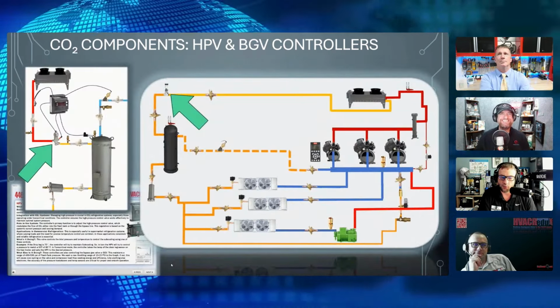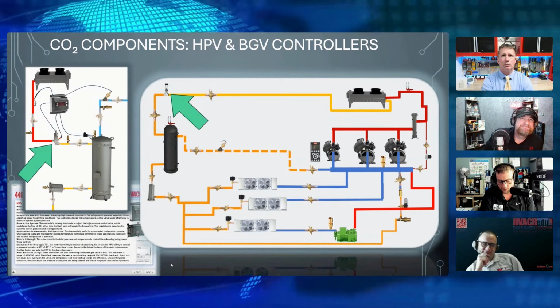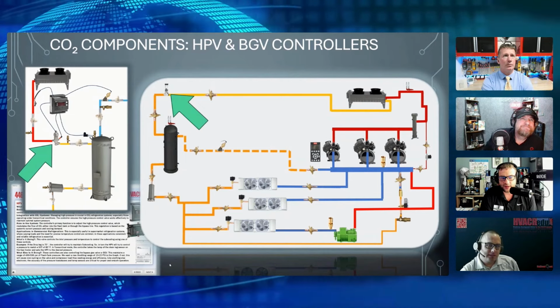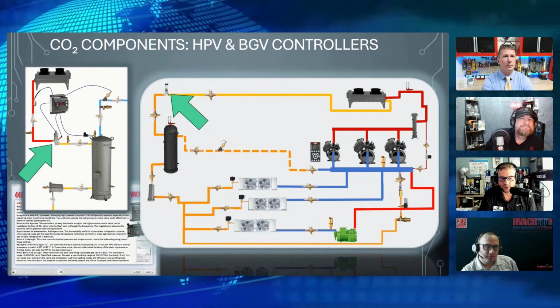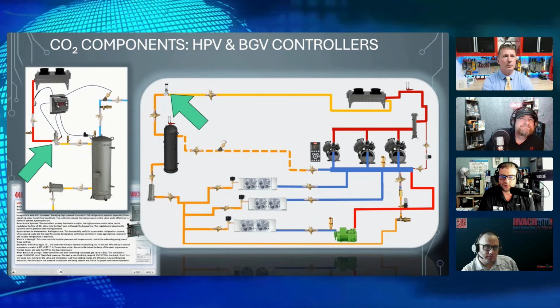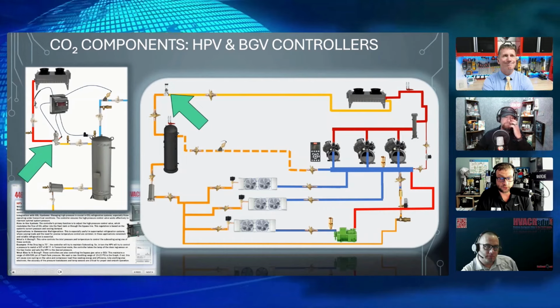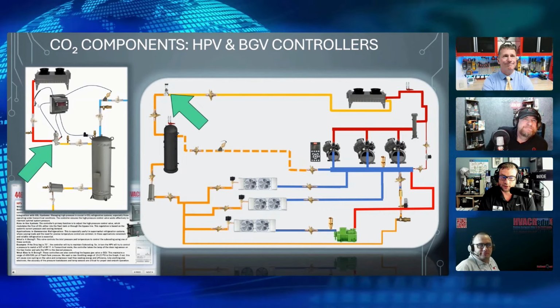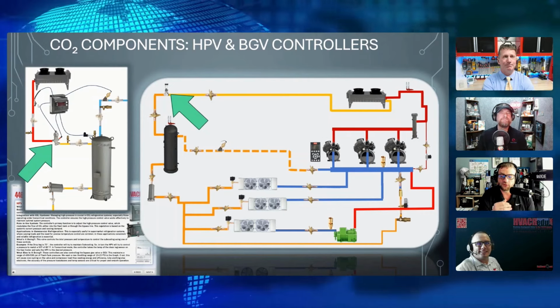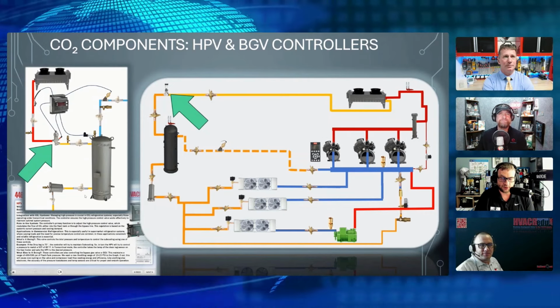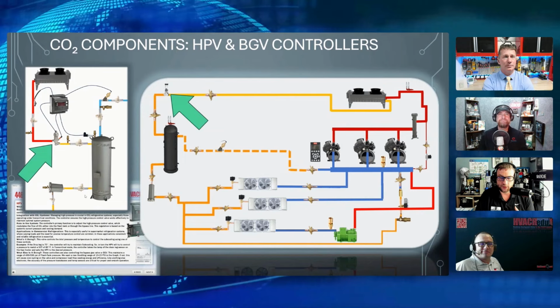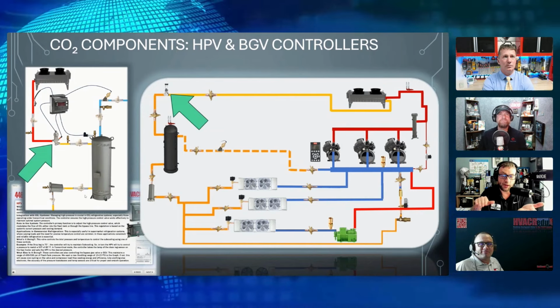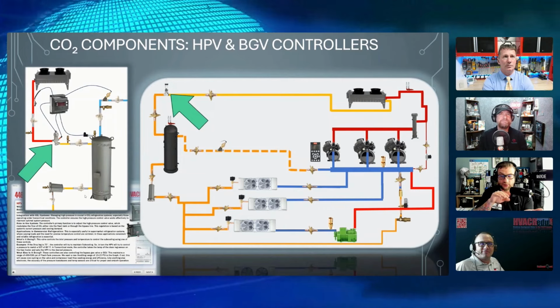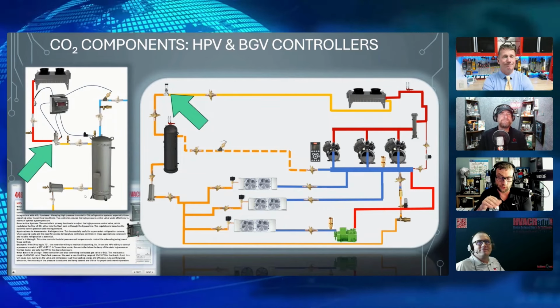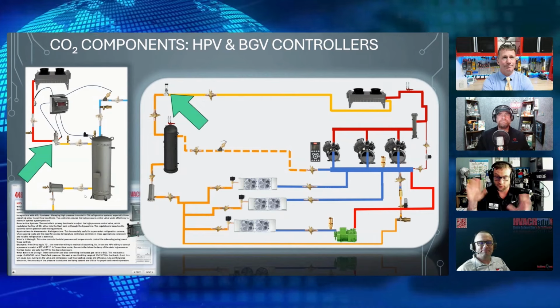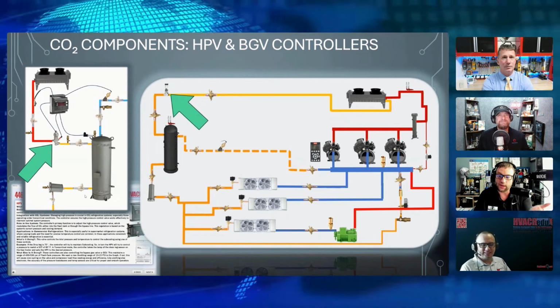Okay, you already got it. If you look at the little picture on the left, that's the HPV. It's just a different style of HPV. It has a pressure transducer right at the top there going to the controller. It also has a drop leg temperature sensor. Typically, this is a formulated way to figure out what the saturated condensing temperature is. So in subcritical operation, the controller looks at the drop leg temperature sensor, and it's like, okay, I'm at 75, so I might have a set point of 5-degree subcooling. It's actually a subcooling mitigation valve when it's running subcritical, because it knows there's liquid being created at that point. It's not Schrodinger's cat, right? We know that we can create liquid at this point.